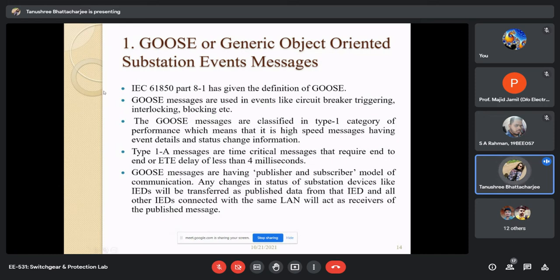These things can be done with the help of IEDs and GOOSE messages. This is a protection type critical message, time critical message, which should travel between 4 milliseconds. So these GOOSE messages are also publisher subscriber messages.